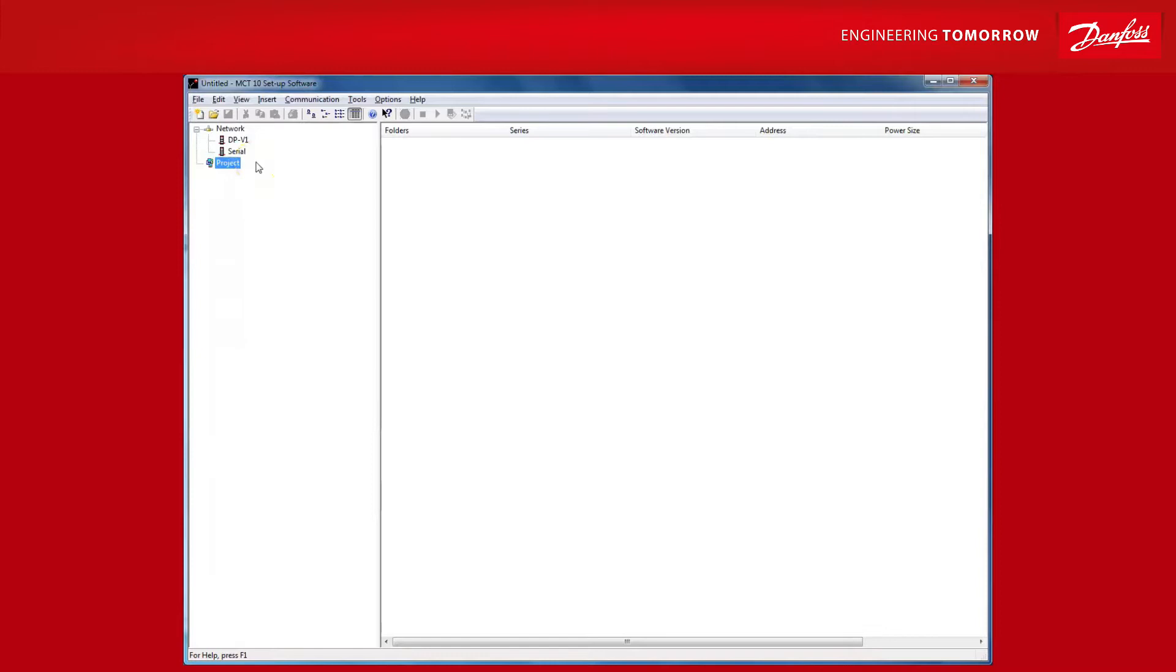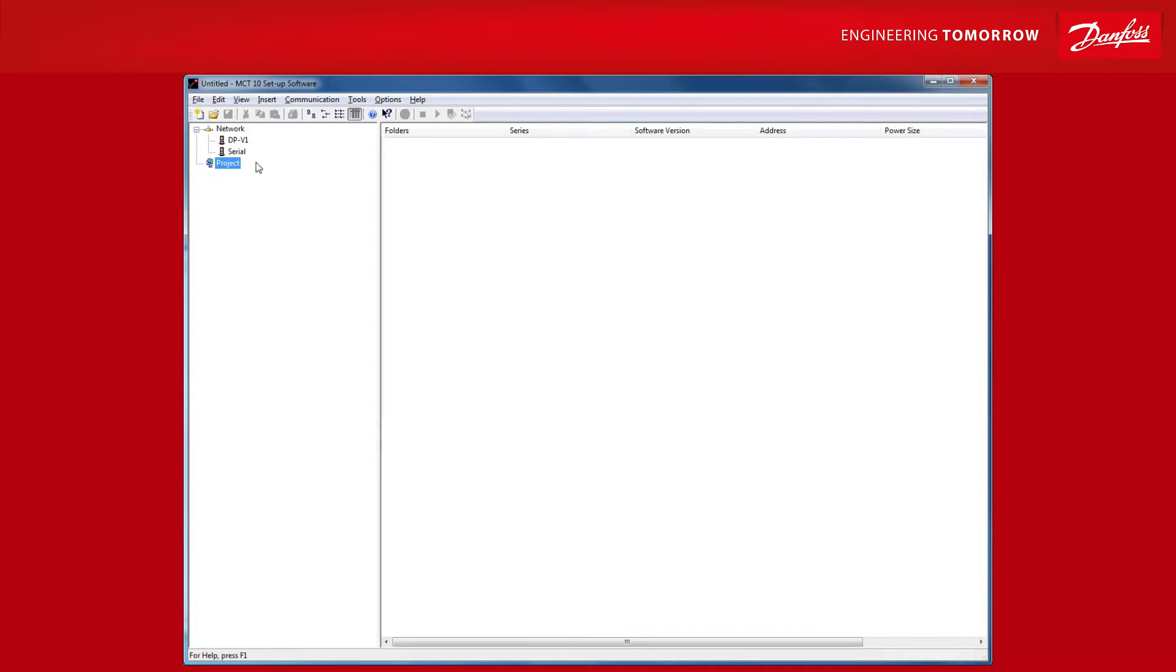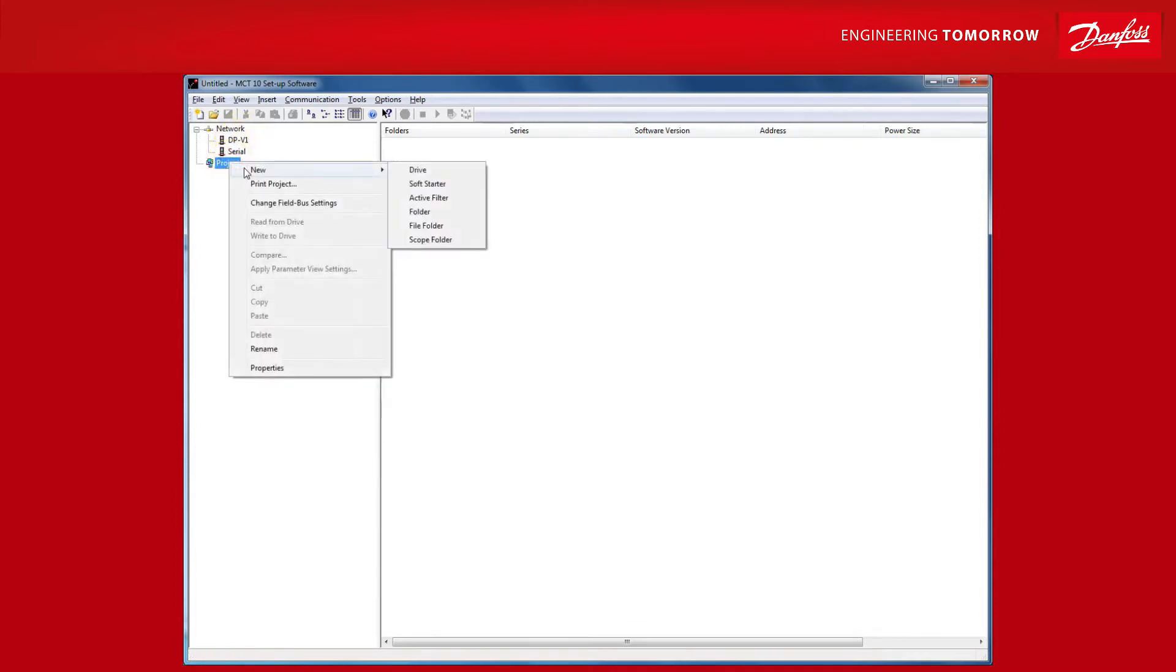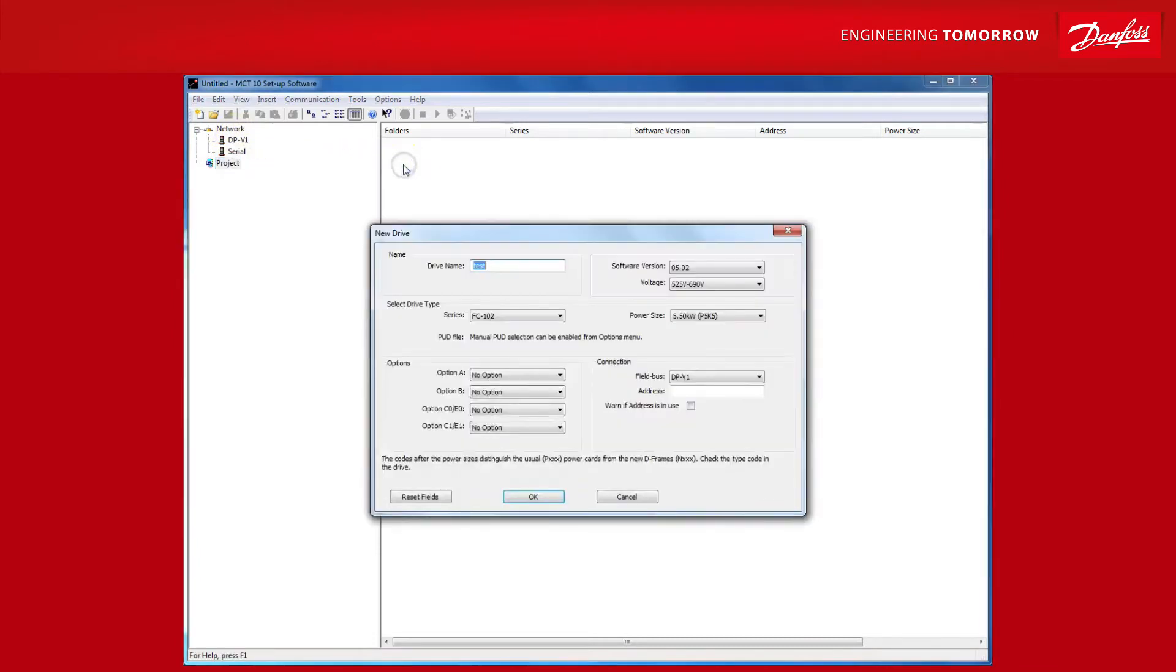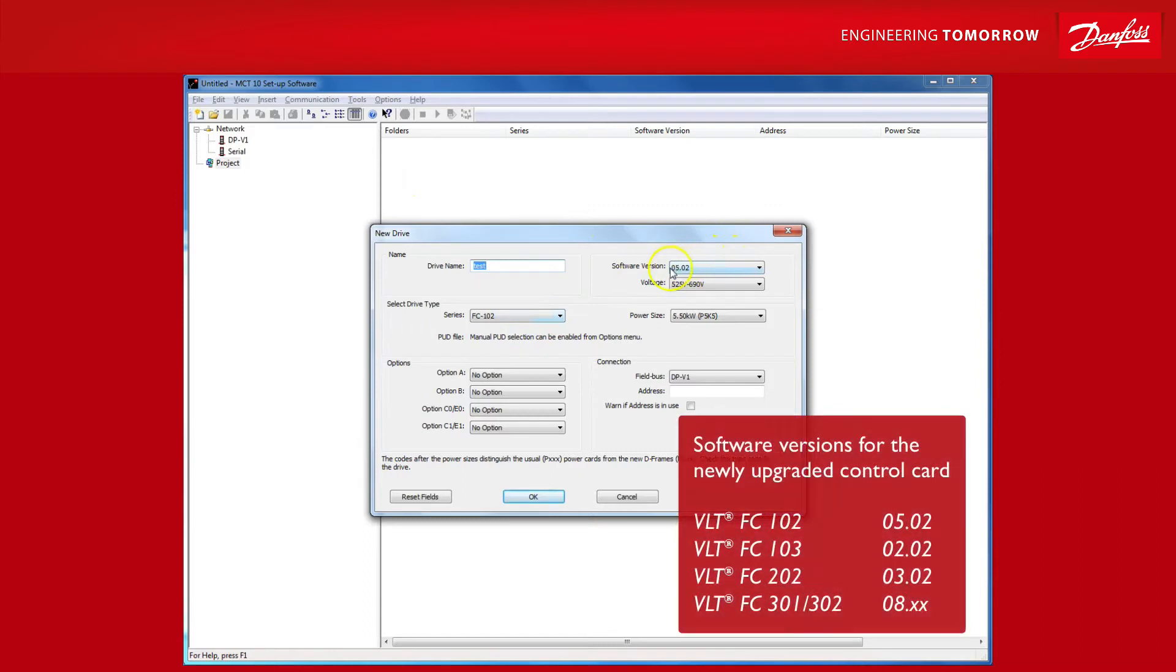Then you need to have the advanced license of MCT10 and you need to purchase this separate license for the VLT software customizer. As you may have seen in the general introduction video for MCT10 4.0, the VLT software customizer is available offline in the project folder. You can either drag and drop a drive you are connected to or you can create a drive from the database. Just make sure to select a software version based on the newly upgraded control card.